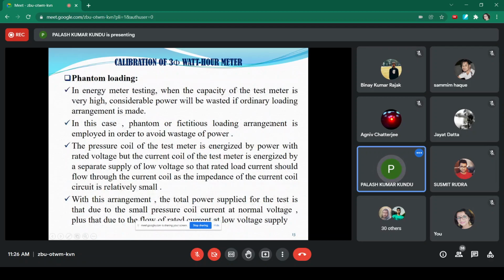Why is phantom loading necessary? For energy meter or wattmeter testing, in the case of actual loading, a certain amount of power loss will occur over the meter as well as the load. But using phantom or fictitious loading, there is no physical load connected to the meter. Instead, the current coil is excited varying from 0% to the rated condition, while the potential coil is excited at a fixed rated voltage. This results in the minimum power loss, and the capacity of the power supplies will be minimum using the phantom loading circuit.